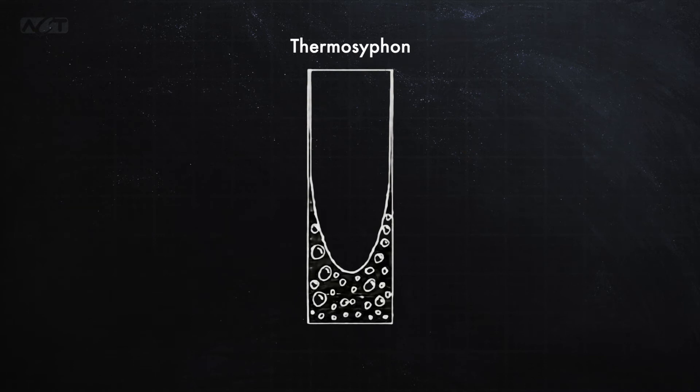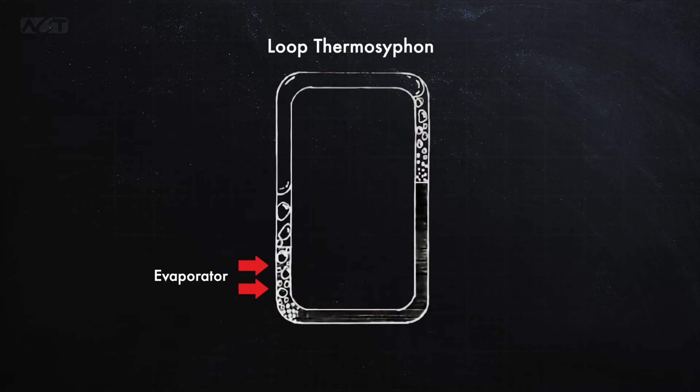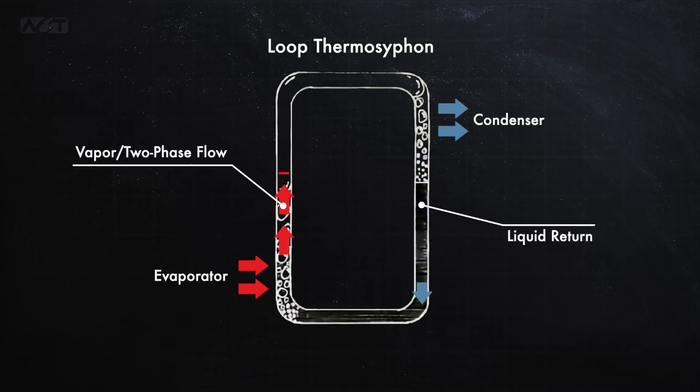A loop thermosyphon operates like a traditional thermosyphon where a two-phase working fluid is transferred from an evaporator to a condenser by taking advantage of the density difference between the liquid and vapor phases. However, unlike a traditional single-tube thermosyphon, the liquid and vapor phases do not flow in the same tube. Rather, the vapor and liquid tubes create a loop giving this thermosyphon its name.